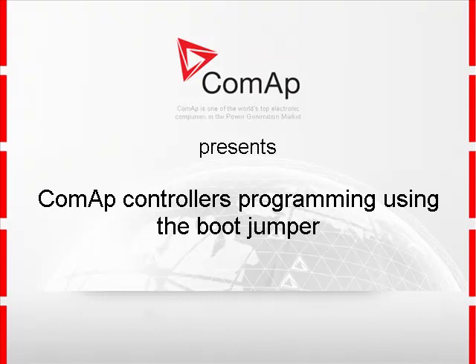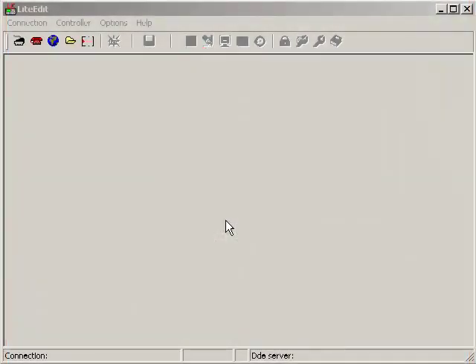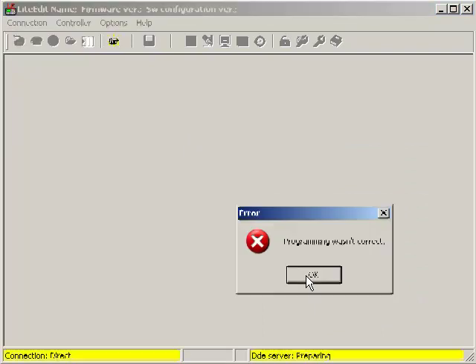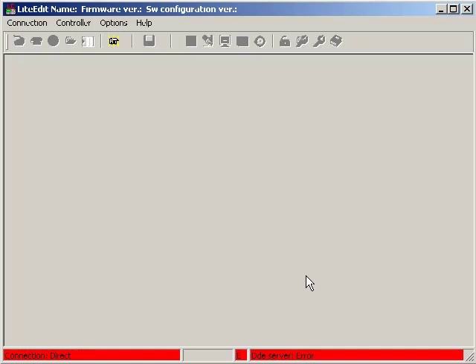Let's start with ILNT control programming using the LiteEdit software. I am in LiteEdit now and I am about to try to open connection to a control which was not programmed successfully. The message 'programming was not correct' is displayed and LiteEdit is not able to open connection to the controller, as you can see.